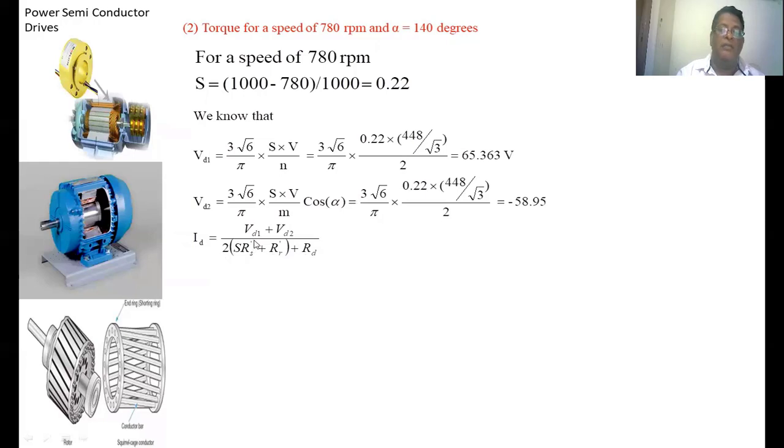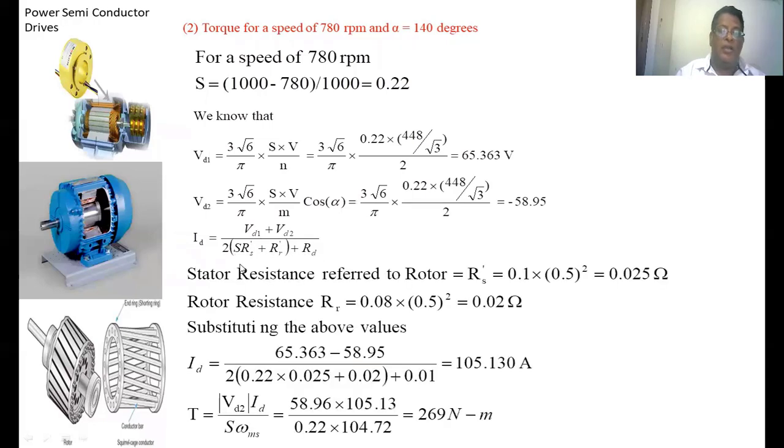We know the expression for DC link current: Id = (Vd1 + Vd2)/(2(S·Rs' + Rr) + Rd). Here Rs' is the stator resistance referred to the rotor. In the numerical, the value is given referred to the stator, so we have to convert it: Rs' = 0.1·(1/2)² = 0.025Ω. Similarly, rotor resistance referred to rotor: Rr = 0.08·(1/2)² = 0.02Ω. Substituting all values in this expression, we get DC link current Id = 105.130A.